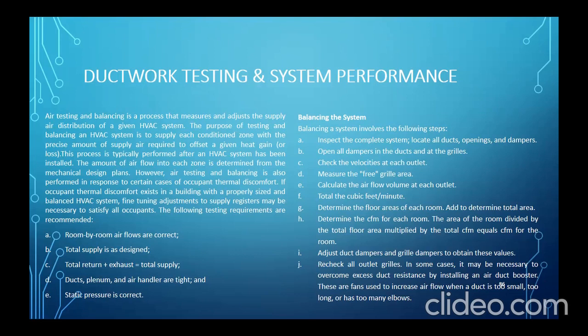Okay? B, open all dampers in the duct and at the grills. C, check the velocities at each outlet. Open dapat yon. Measure the free grille area. Okay, free grille area, yung mga iba yung grills mo, yung mga harang-harang yan. So, tanggalin mo yung harang na yon. Okay? Calculate the air volume at each outlet. So, total the cubic feet per minute.